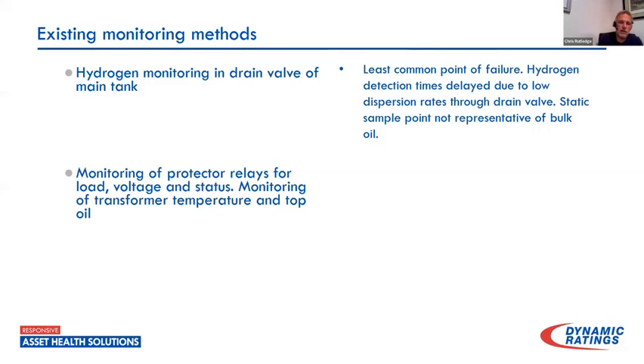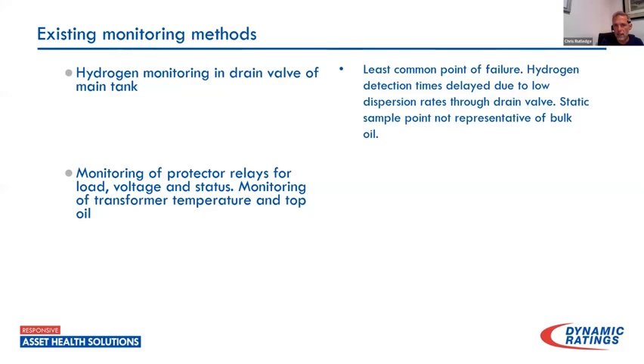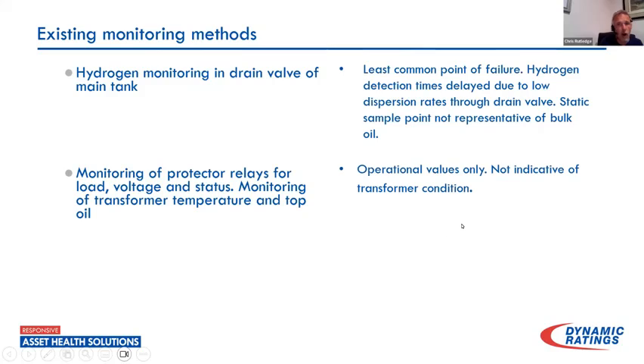Monitoring of the protector relays gives us an idea of voltage, load, and status — is this protector in or out of the grid right now. Some people would even bring in transformer oil temperature, top oil. These are all critical things to know about your transformer. However, these are really operational values. I can't really remember a lot of events where top oil would have tipped me off that I was going to have a failure.